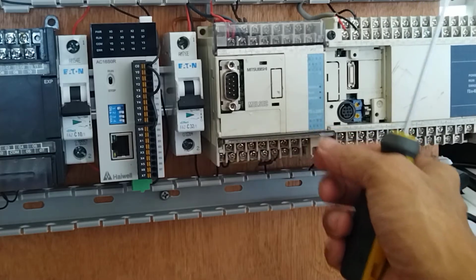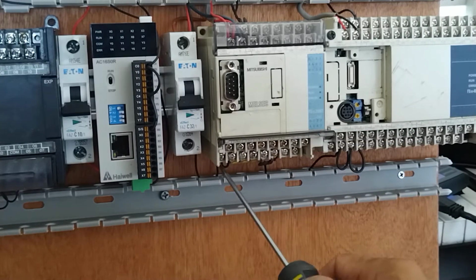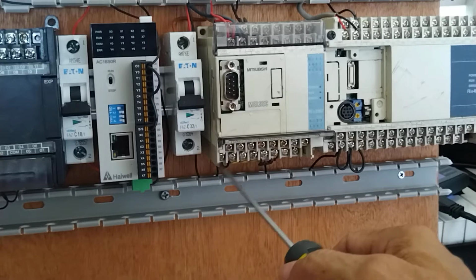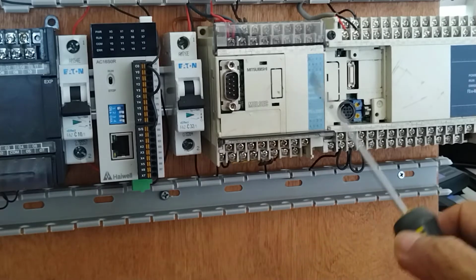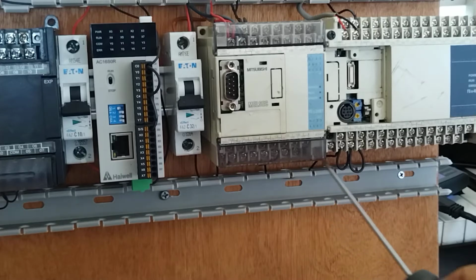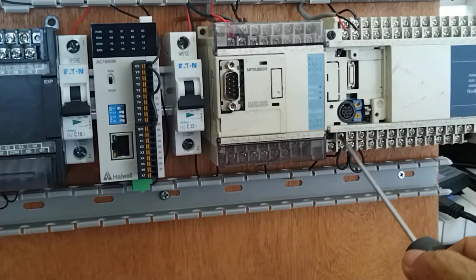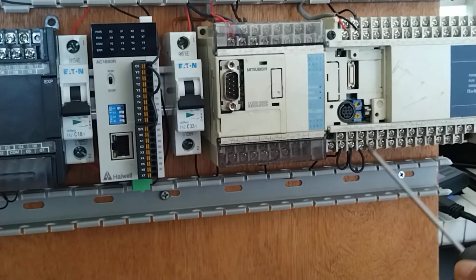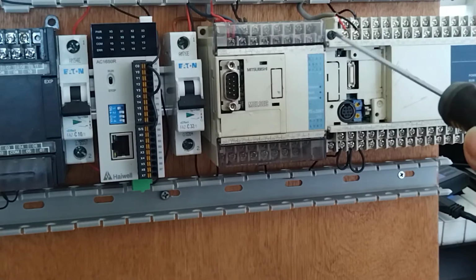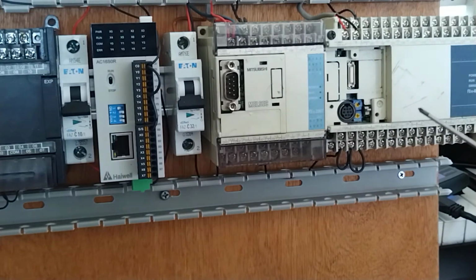There will be a provision here for 24 volts output, but the ampere rating is very low. Likewise, there's 24 volts available at the lower terminal. Just like the other PLC, you need to distinguish which terminals are labeled for power, so you know which one is the power source, because you don't want to damage your PLC by providing the wrong power to the wrong terminal. This is the most important part here.